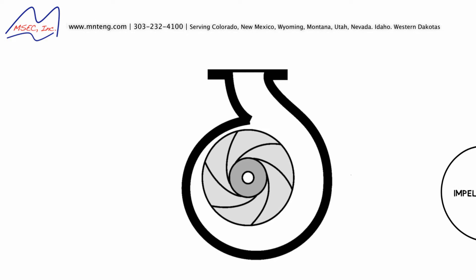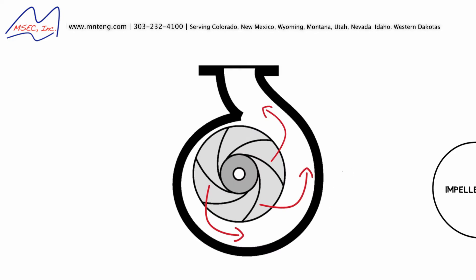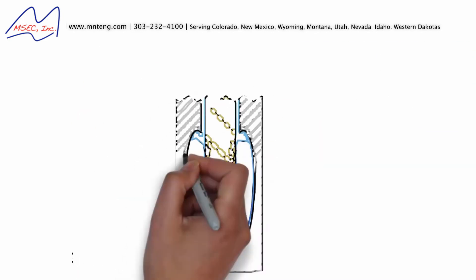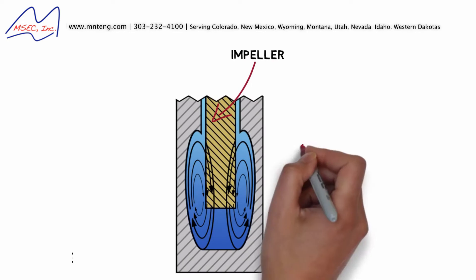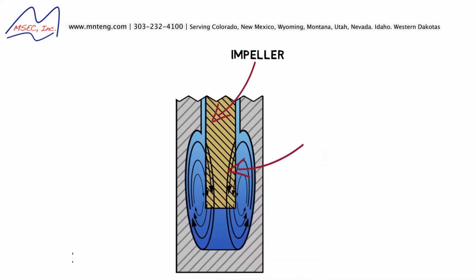Liquid entering a centrifugal pump's impeller can pass between the vanes only once. Energy is added to the liquid as it travels from the center of the impeller to the rim. In a regenerative turbine pump, liquid recirculates between the impeller's vanes. This helical action carries the liquid forward.